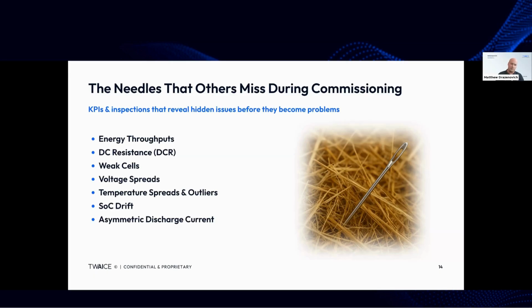With that, we also look for weak cells, which might indicate loose interconnects more at the cell level. Voltage spreads is more along the lines of wanting to understand if the voltages within a string are all essentially equal throughout the discharge or charge profile, which if they're not, will definitely lead to capacity loss in the future. Also temperature performance.